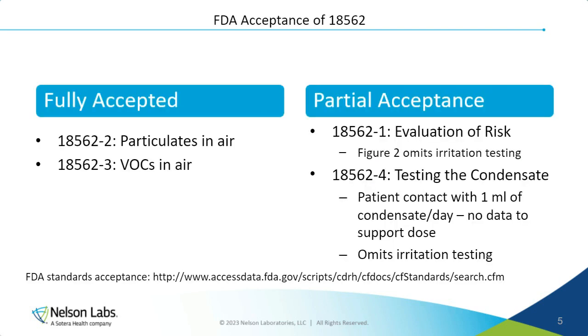Furthermore, the FDA fully accepts 18562-2 and 18562-3, and it partially accepts -1 and -4. In -1, the FDA omits the irritation testing, and in -4, the FDA omits irritation testing and the worst case patient contact of 1 ml of condensate per day. They state there is not enough data to support this condensate dose. In lieu of -4, ISO 10993-18 may be a substitute for the FDA submissions.